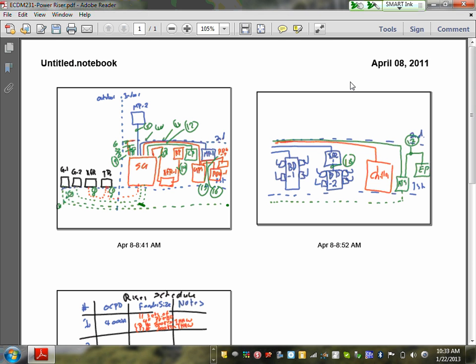What happens is you have to pick up this life safety circuit over here. Code says once you lose utility, this has to be up and running within 10 seconds. The rest of the building could take 30 or 40 seconds or whatever. It doesn't matter because it's standby. You're just trying to not have the whole building in the dark. So one of these two generators, Gen 1, you'll probably have a second breaker for life safety feeding this transfer switch over here, and then you'll have a breaker from the utility side feeding that transfer switch.